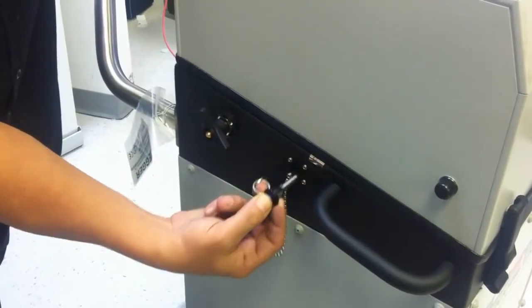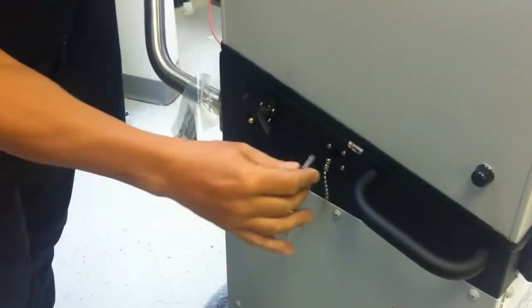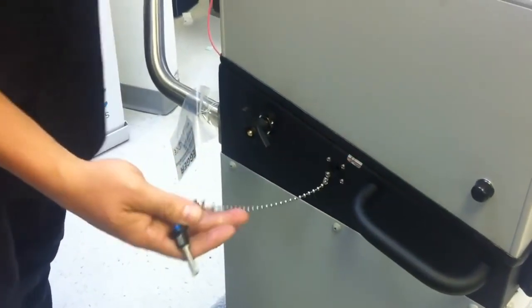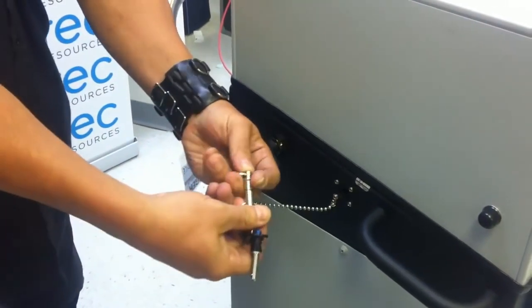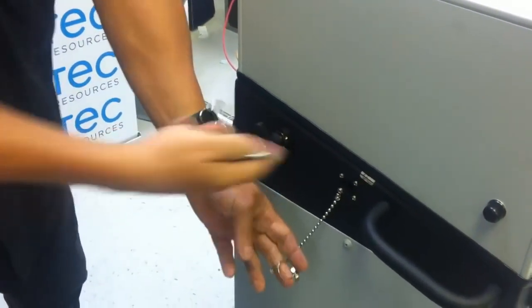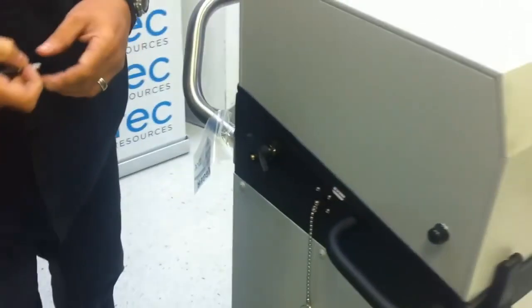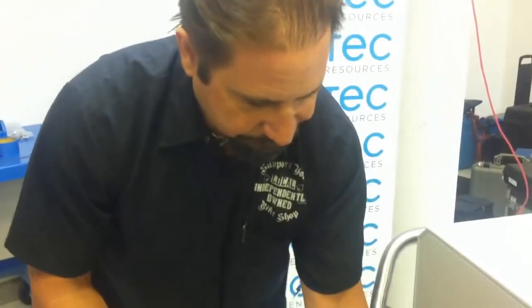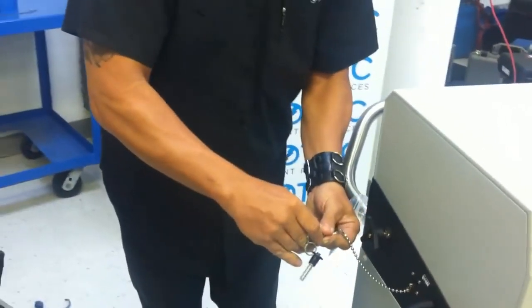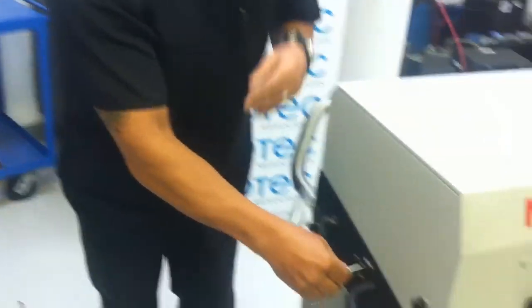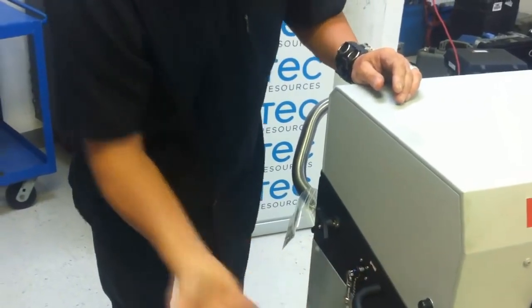This little plug serves as the system interlock. When the plug is pulled out, for safety purposes, I can take it along with me. The instrument will not engage, will not go to a high voltage state until the interlock is once again returned.